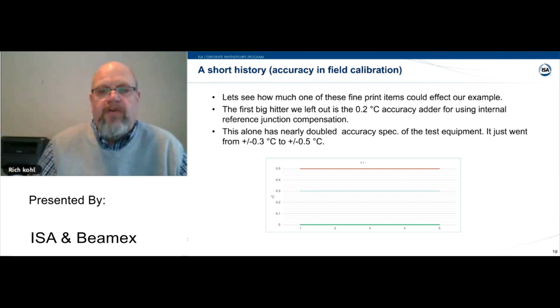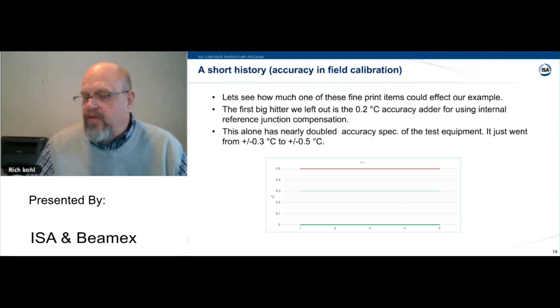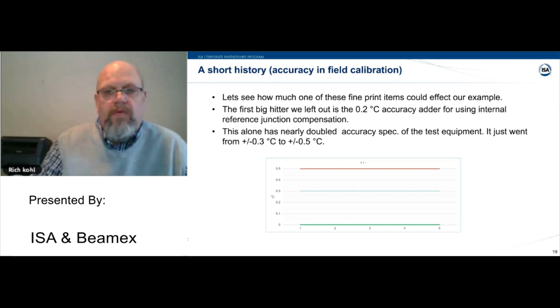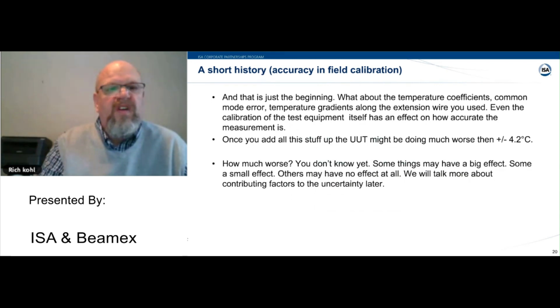If you didn't use that, you would have created an external reference junction compensation, which has its own sources of uncertainty, which you would have to add besides that. So now we're looking at this increase of spec just from the point of view of the measuring and test equipment. In this case, you started out at 0.3, and you've gone up with a 0.2 adder to 0.5. You've almost doubled your specification of your calibrator, and this is just looking at one of the components of contributing factors to your calibrator's accuracy. So that's just the beginning.